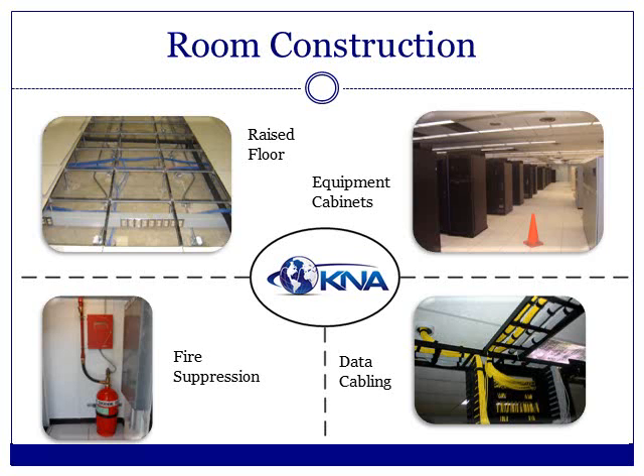One of the most overlooked factors in designing the data center environment is the hazard of fire. Stricter fire codes across the country are now requiring the use of things such as suppression systems, detection, alarms, emergency power-off devices, and portable extinguishers. Suppression system options range from wet and dry sprinkler systems, pre-action systems, clean agent systems, and wet and dry chemical agents. We will consider all relevant factors to determine the best options and designs to protect the physical well-being of the data center and its critical assets.